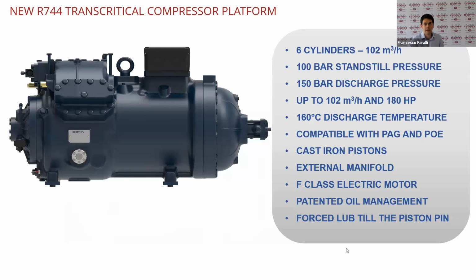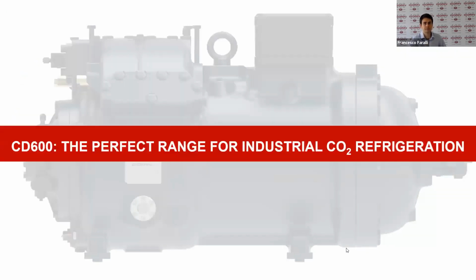Here, to summarize, this is the CD600, the largest transcritical CO2 compressor available in the market, up to 102 cubic meters per hour, 100 bar standstill pressure and 150 bar discharge pressure. The electric motor is 180 horsepower, and the maximum discharge temperature is 160 degrees Celsius. All these compressors are equipped with the technical features that I have explained before.